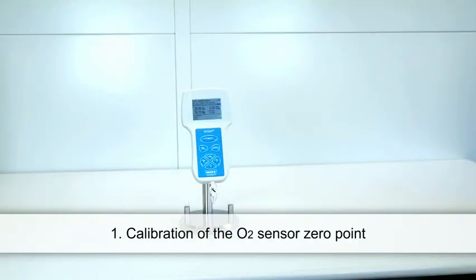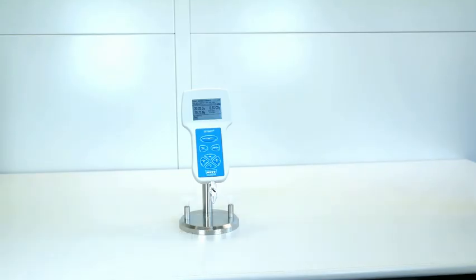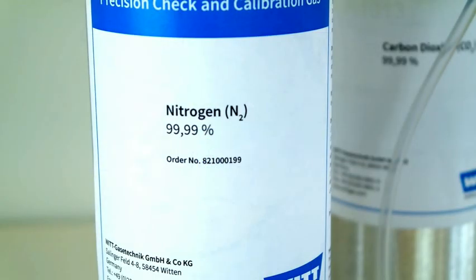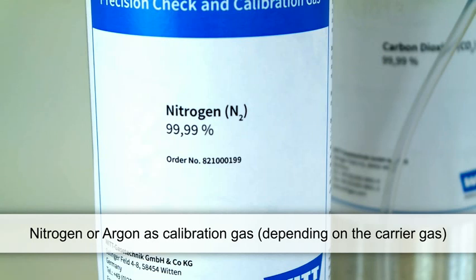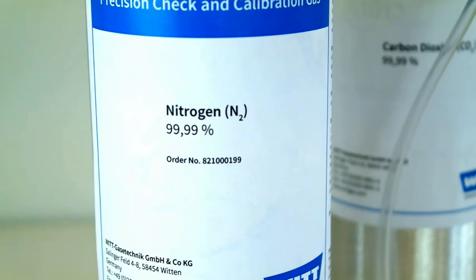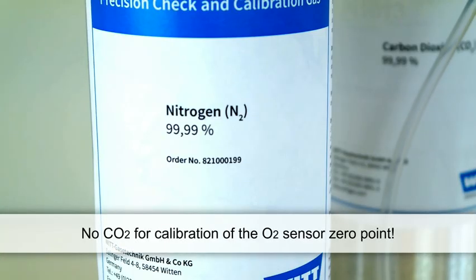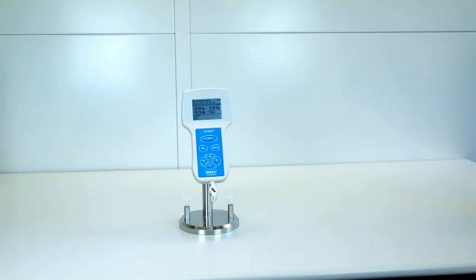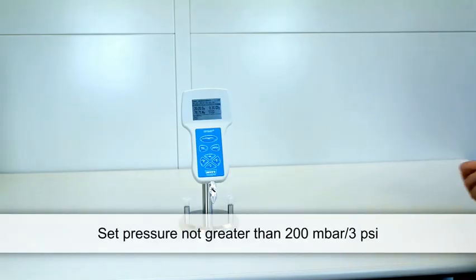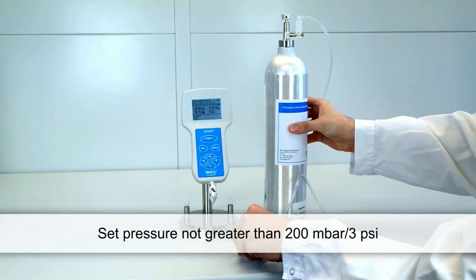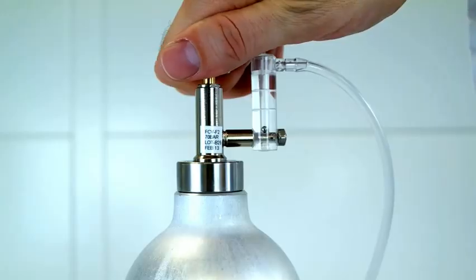When calibrating the 0 point of the O2 sensor, use a suitable gas cylinder with a pressure-reducing regulator. The choice of the gas to be used depends on your application and the carrier gas you use. For the calibration of 0 points, we recommend commercial nitrogen or argon. Never use high-purity CO2 for the 0-point calibration of the oxygen sensor, as this may result in incorrect measurements. Now set a very low pressure with the pressure regulator set no higher than 200 mbar or 3 psi.